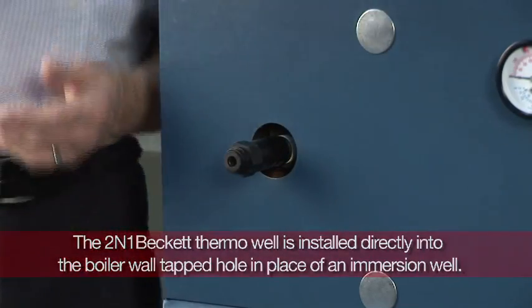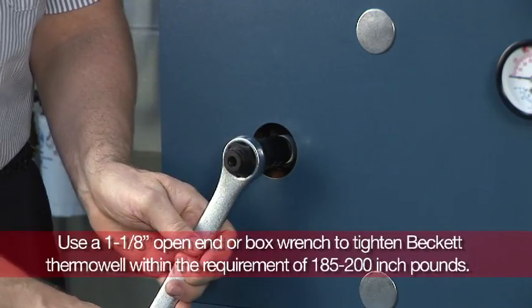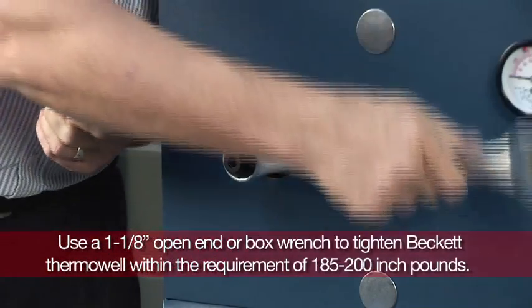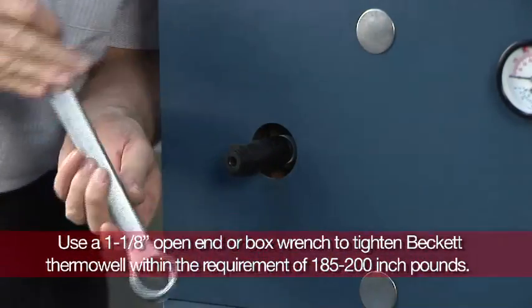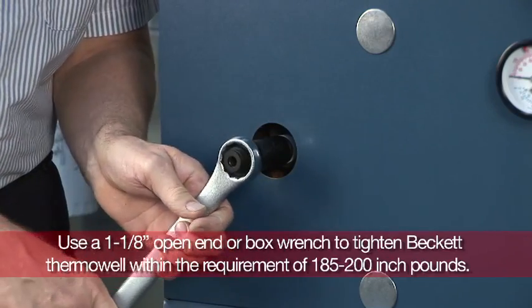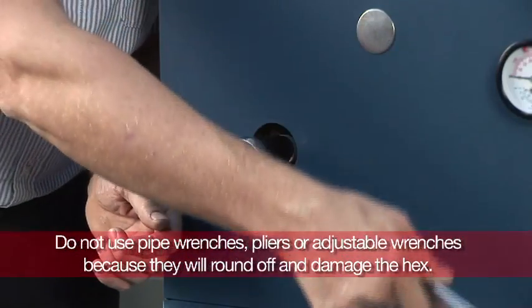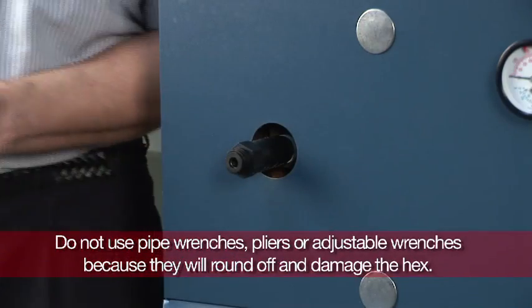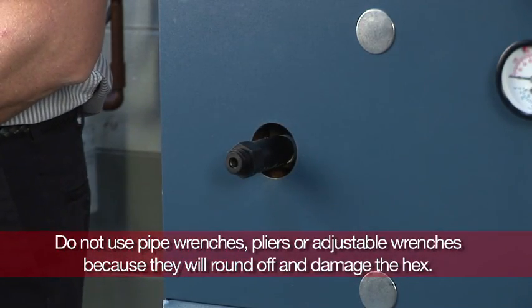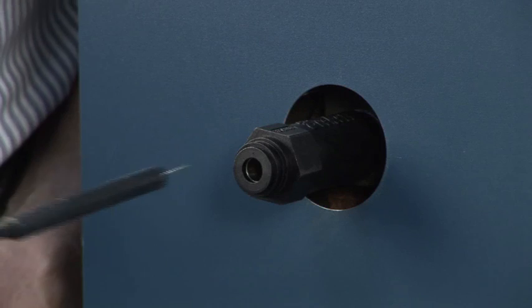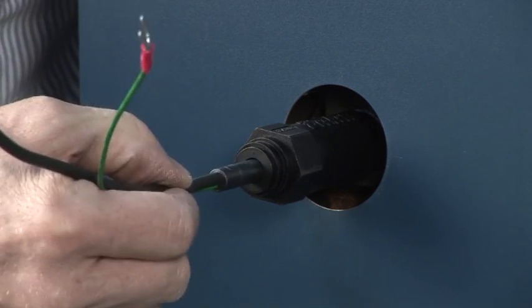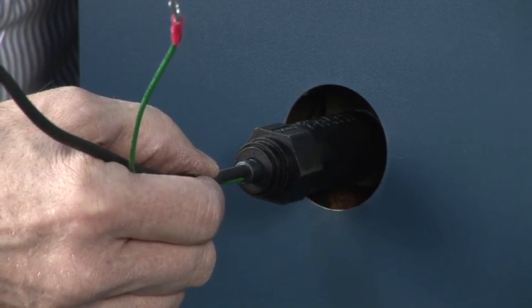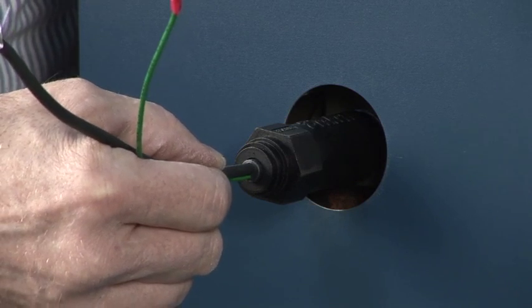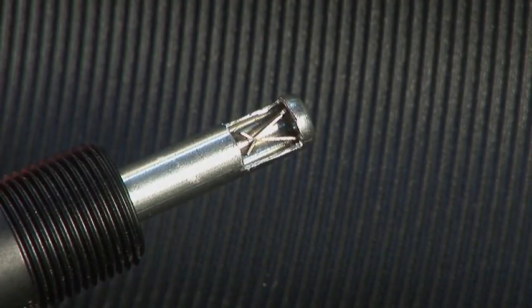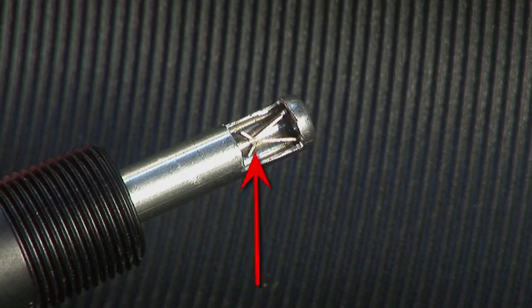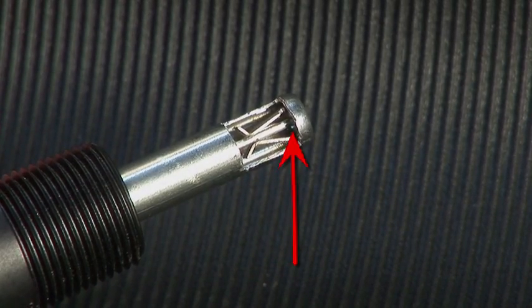The 2-in-1 Beckett thermowell is installed directly into the boiler wall tapped hole in place of an immersion well. Use a 1 1/8-inch open end or box wrench to tighten the Beckett thermowell within the requirement of 185 to 200 inch-pounds. Do not use pipe wrenches, pliers, or adjustable wrenches because they will round off and damage the hex. Next, insert the temperature sensor probe into the thermowell until it comes into contact with the clip opening and there is some slight resistance. Continue pushing the probe until it completely bottoms out into the end of the thermowell.